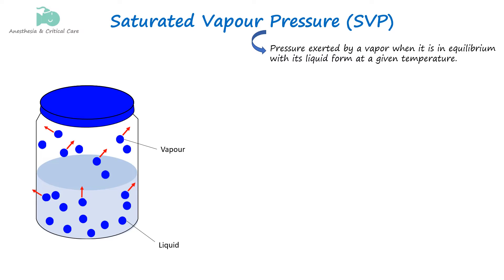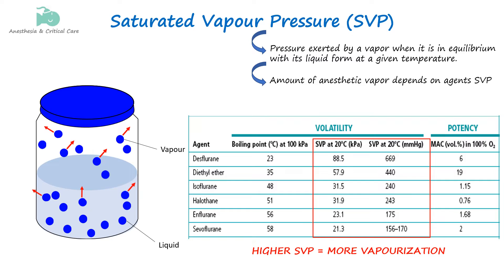The pressure at this point is called saturated vapor pressure (SVP). SVP is important because it tells us how easily a substance can turn into vapor at a specific temperature. Each anesthetic agent has a unique SVP, so vaporizers need to accurately control the amount of vapor released based on the SVP of the agent at room temperature.